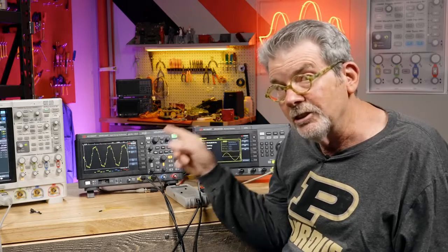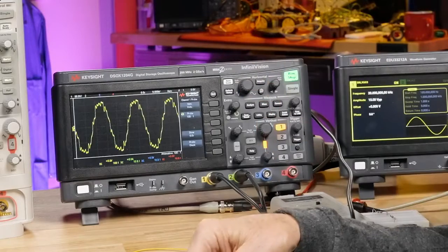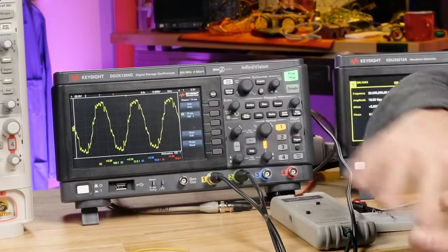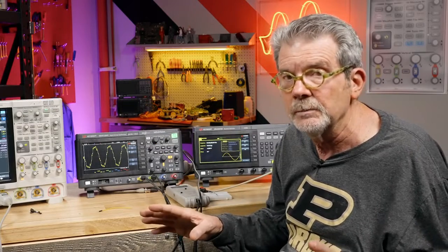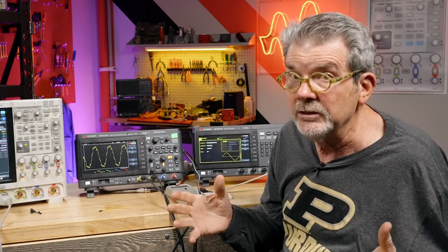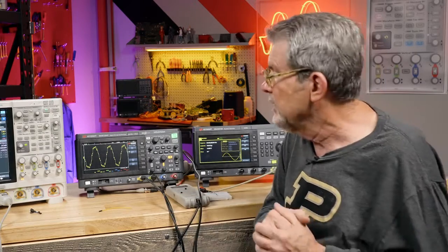This is the AC input in this room. It is really ugly. Look at all that interference or garbage riding on that sine wave. I've seen it in this building before. I did this test at home yesterday. I had a pretty clean sine wave in my home lab.